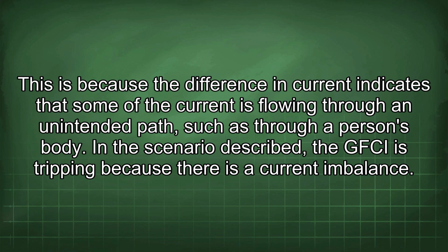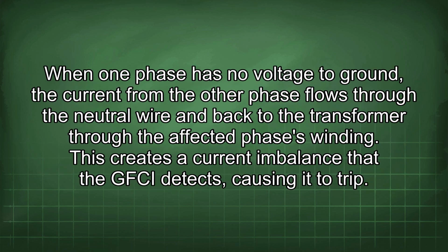In the scenario described, the GFCI is tripping because there is a current imbalance. When one phase has no voltage to ground, the current from the other phase flows through the neutral wire and back to the transformer through the affected phase's winding. This creates a current imbalance that the GFCI detects, causing it to trip.